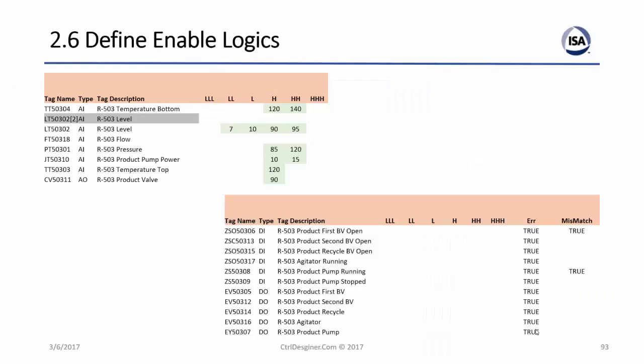Now, the next part is the advantage of procedural control over loop-based control is that you don't go and put all of the alarms on, 6 alarms for every instrument, and then go and come up with alarm reduction systems and things like that.